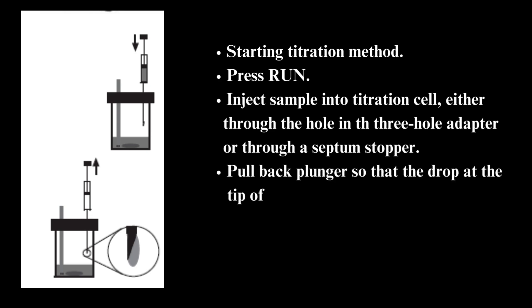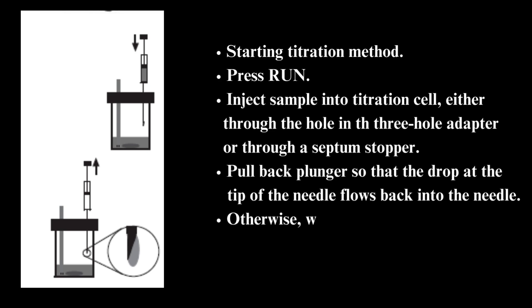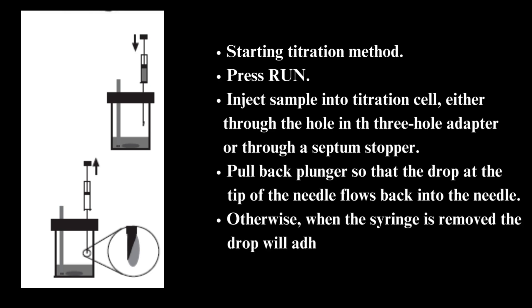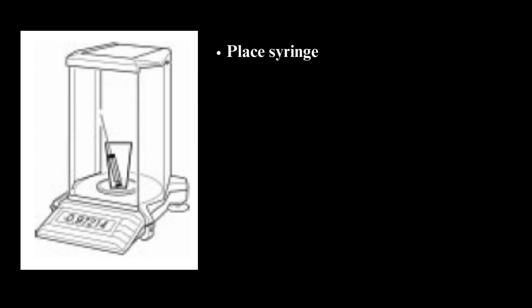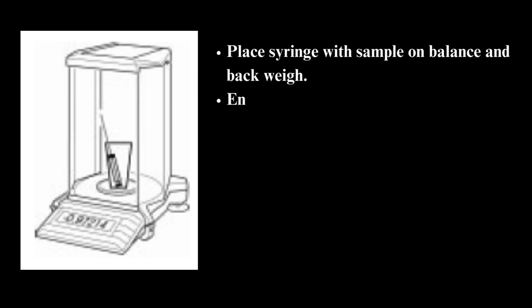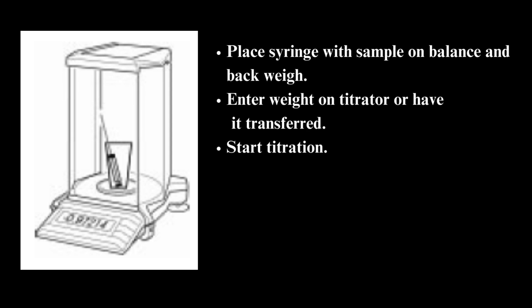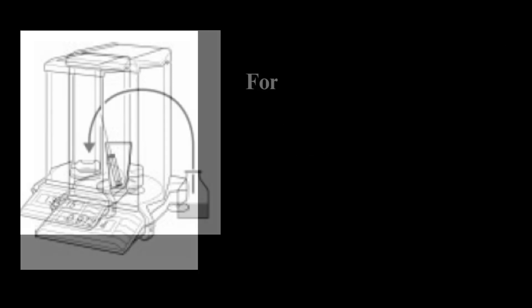Pull back the plunger so that the drop at the tip of the needle flows back into the needle. Otherwise, when the syringe is removed, the drop will adhere to the septum. Place the syringe with sample on the balance and back-weigh. Enter the weight on the titrator or have it transferred, then start the titration.